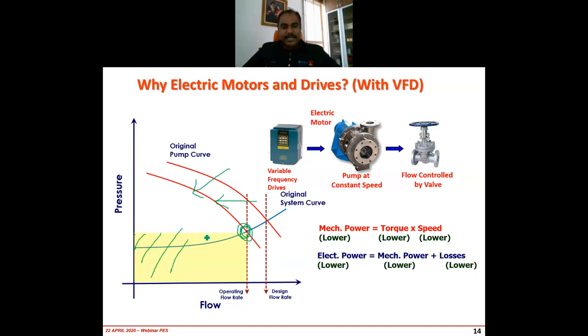That means the mechanical power is going to get smaller. As you can see here, the mechanical power is actually reduced, and that will reduce the electrical power. So this is how we save energy in an electric motor system, provided the system requires some changes. In this case, the pump system requires a change of flow, and therefore a variable frequency drive will definitely help you save energy.